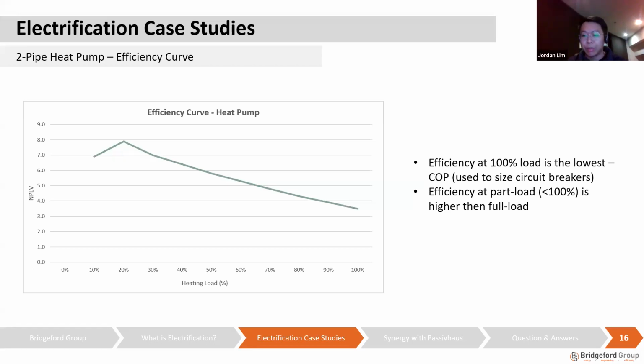I thought I should bring up the efficiency curve of heat pumps a little bit, in case there are people within this audience that are unaware. Heat pumps run best when performing on part load. You can see here that when it's running at 100%, the efficiency is actually not the best. The COP is only about 3.5-ish, but this is just an example. It can go all the way up to 4 or maybe even as low as 2.8. When running at 100% capacity, its efficiency is at its worst, but if it's running on part load, the efficiency keeps going up, right?